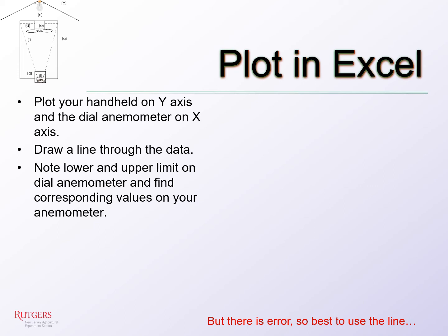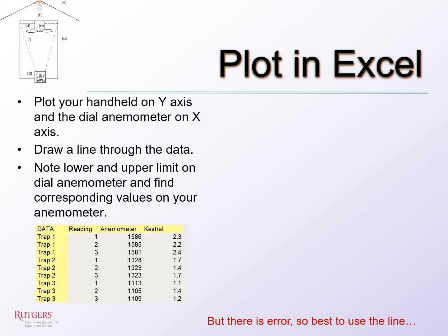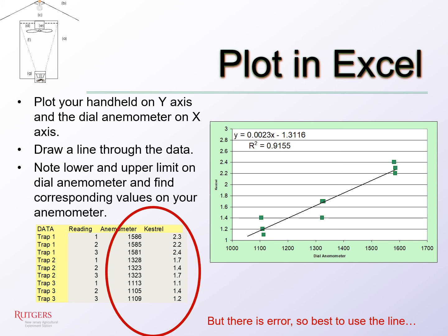Once you have your readings, you can plot your results in Excel. An example can be seen here with the data from the dial anemometer and the handheld in the 2 right columns. Plot as a scatter plot, and then by right-clicking your mouse on the data, select Add a Trend Line. Add the linear trend line and make sure you check the Display Equation on Chart and Display R-squared value on chart options. This will give you the information you need to find the precise upper and lower limits, plus how confident you can be in your handheld.